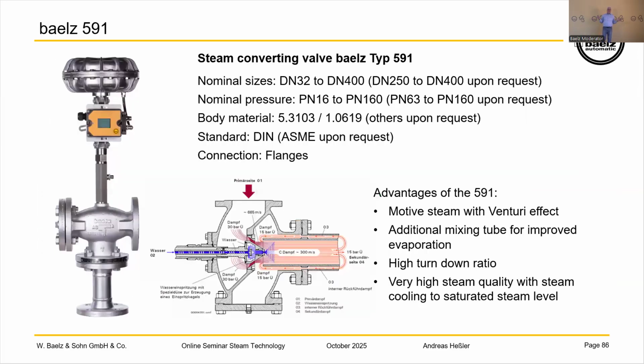And last but not least, I just want to say real quick something about our steam converting valve 591, just for the advantage, what we're doing with them. You see on this picture, we have two different kinds of cooling systems. We're using the motive steam head and also, in case of the protection pipe, what we install, the Venturi system. So we have a very, very good ratio. We can go near saturated steam temperature and a very, very low distance to the temperature sensor.